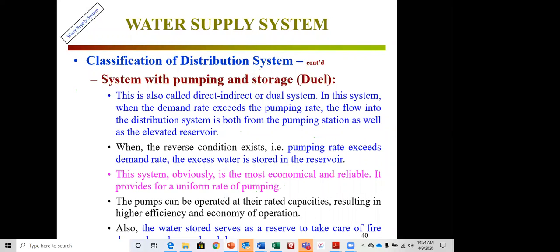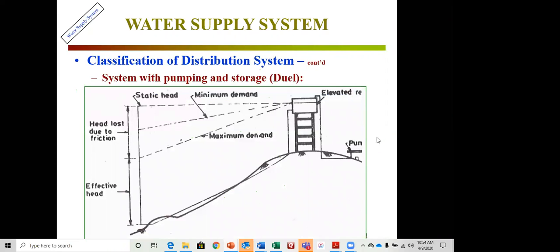The pumping and storage system is a dual system. When pumping rates exceed demand, excess water is stored in the overhead reservoir. When demand exceeds pumping rate, stored water supplements supply. This system combines direct pumping to consumers with parallel pumping to an elevated storage tank, providing flexibility and reliability.